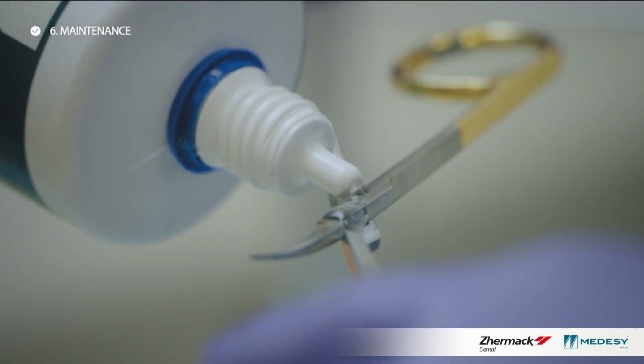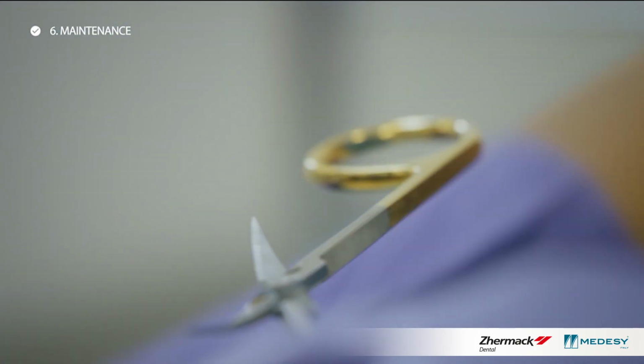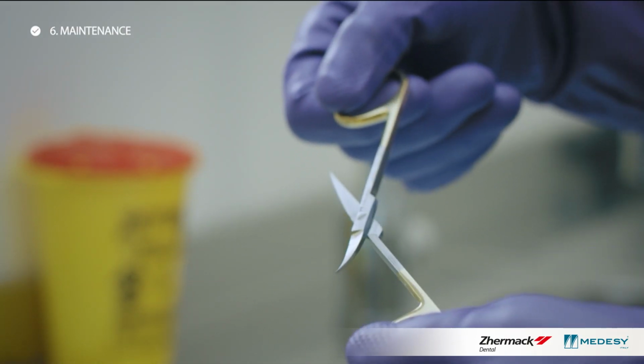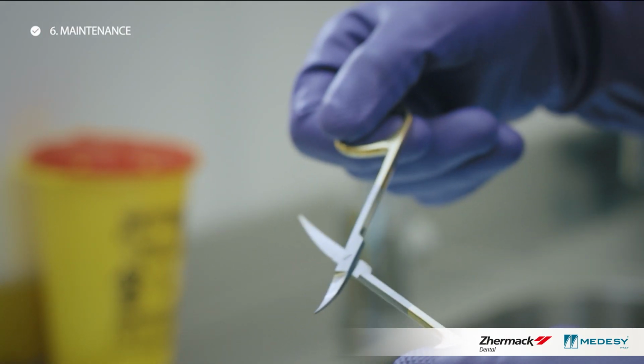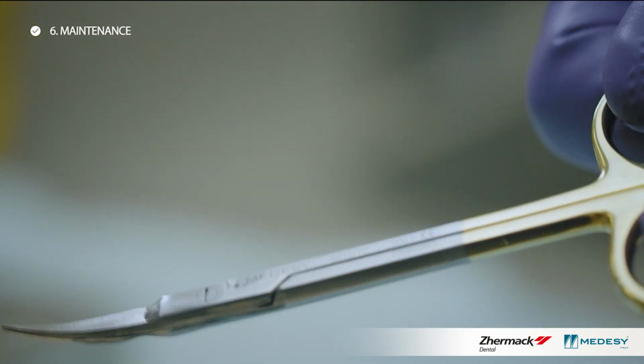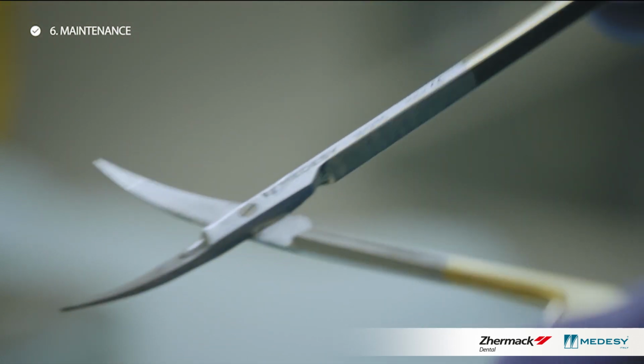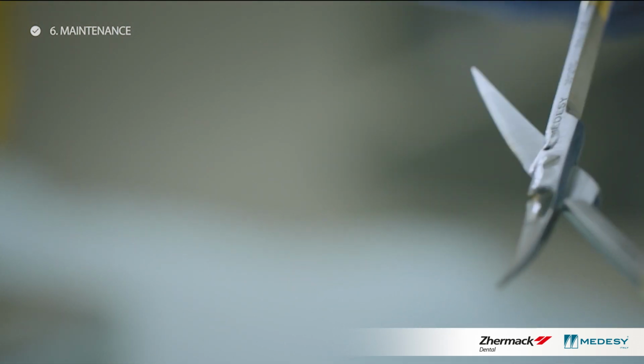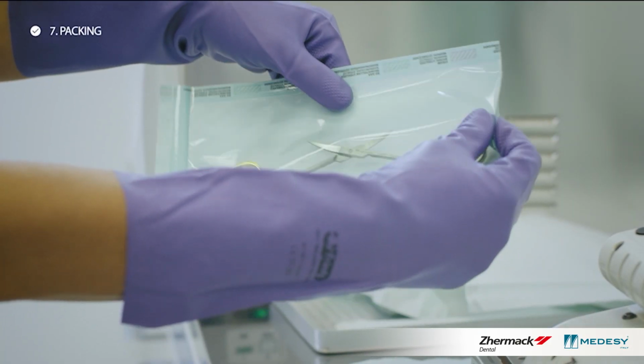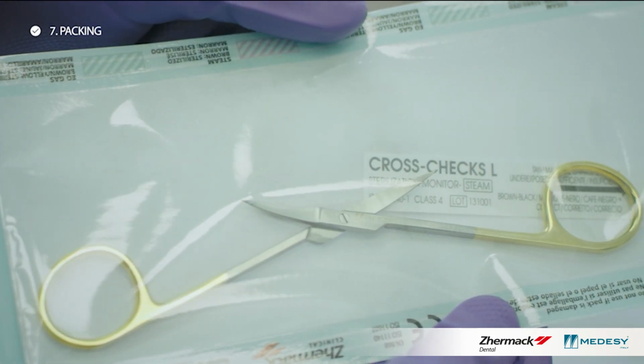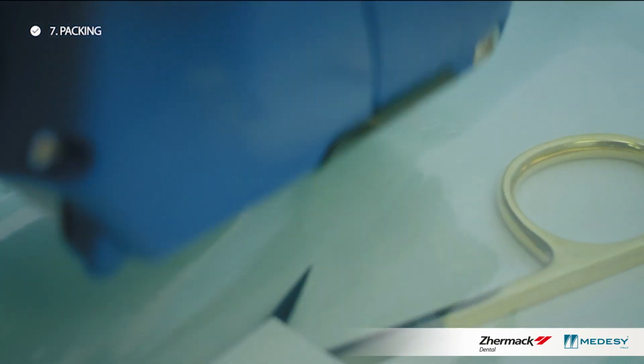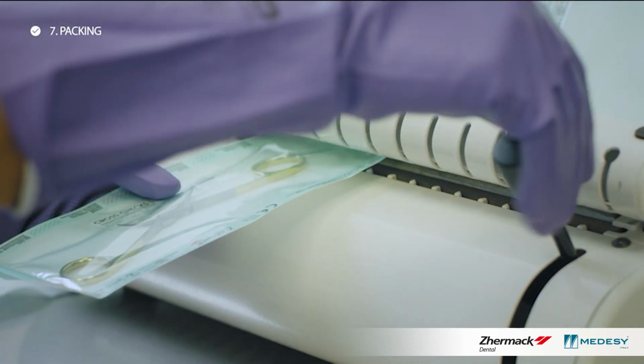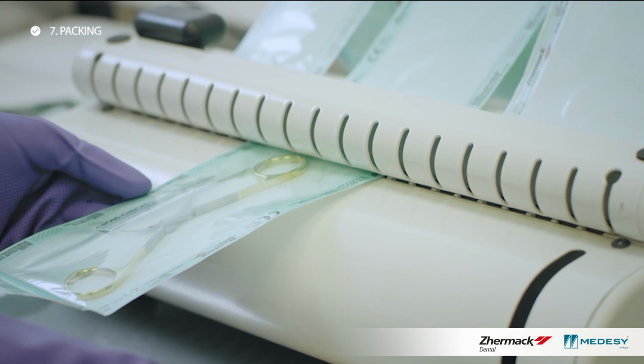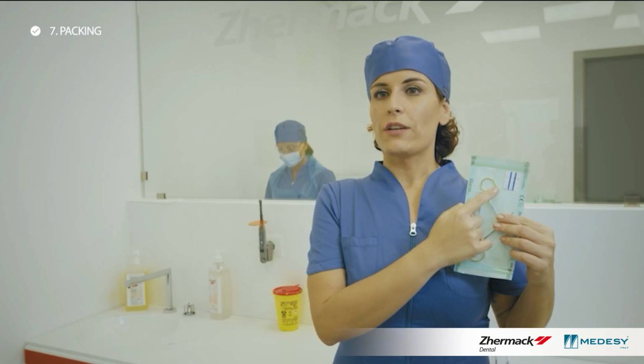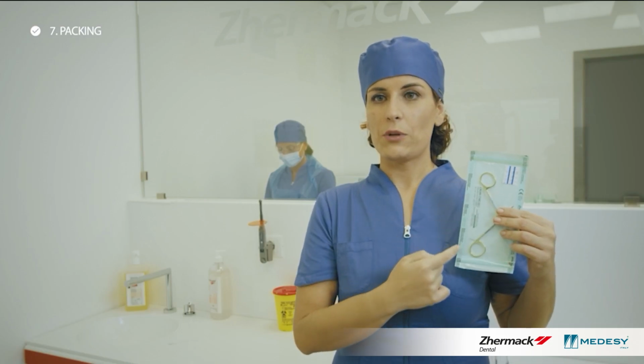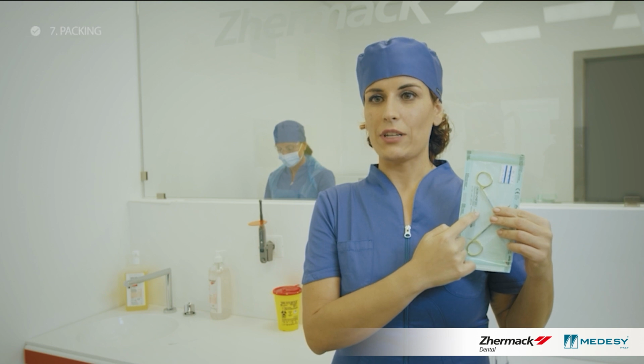Instrument maintenance ensures their durability and guarantees a high-quality service. Apply specific lubricants soluble in cold water. If the material is steam sterilized, the products must be silicone-free. Sort the instruments into pouches. For each pouch, indicate the sterilization and expiry date and the operator performing and verifying the process. All pouches must also have a chemical process indicator and sterilization integrator.